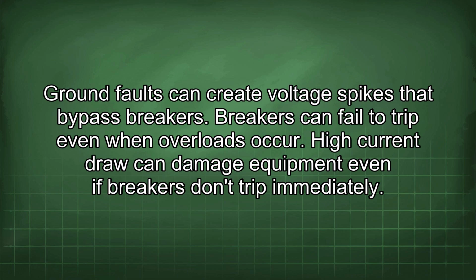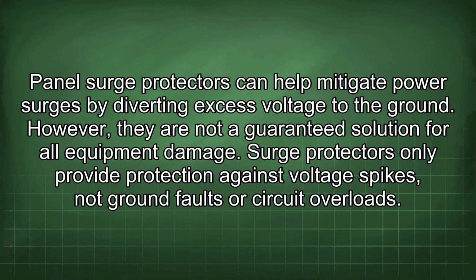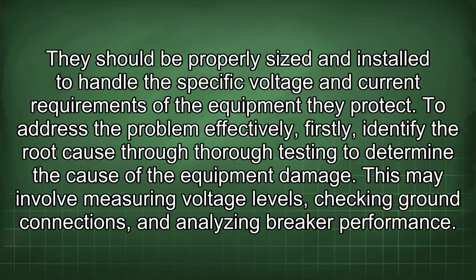Breakers can fail to trip even when overloads occur. High current draw can damage equipment even if breakers don't trip immediately. Panel surge protectors can help mitigate power surges by diverting excess voltage to the ground. However, they are not a guaranteed solution for all equipment damage. Surge protectors only provide protection against voltage spikes, not ground faults or circuit overloads. They should be properly sized and installed to handle the specific voltage and current requirements of the equipment they protect.